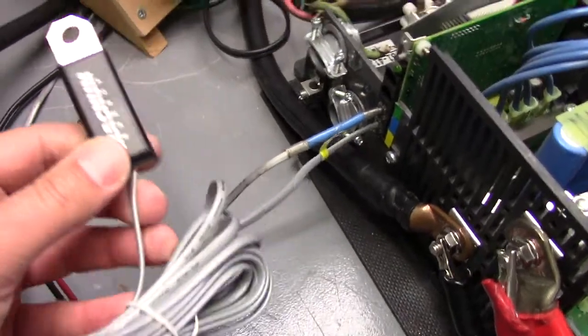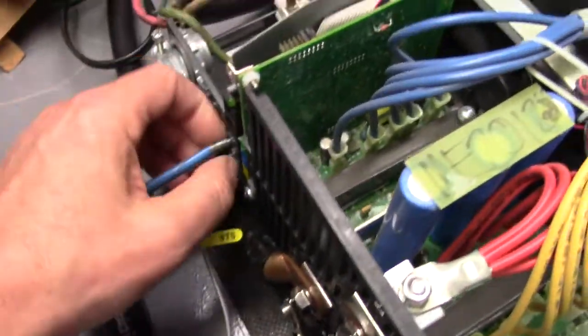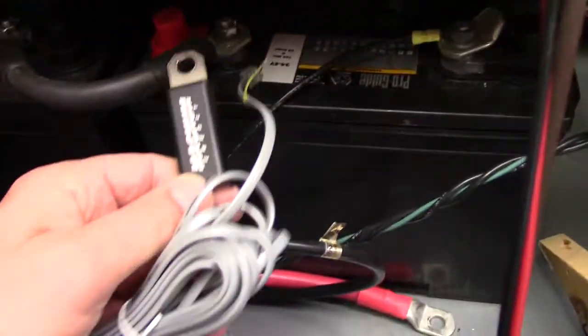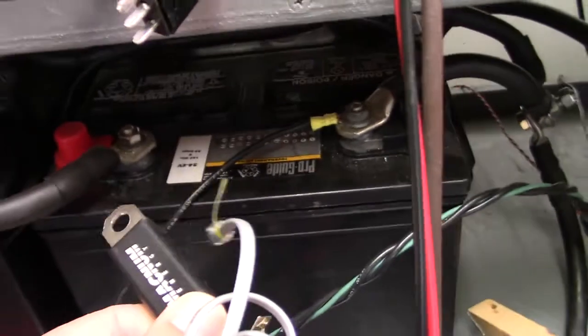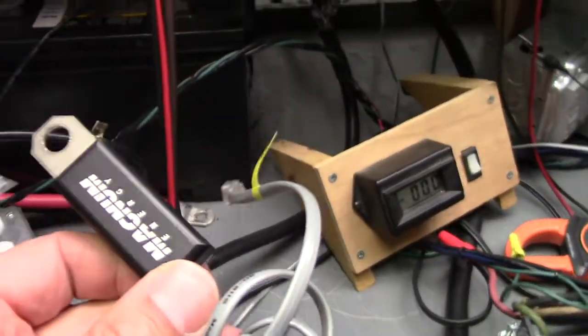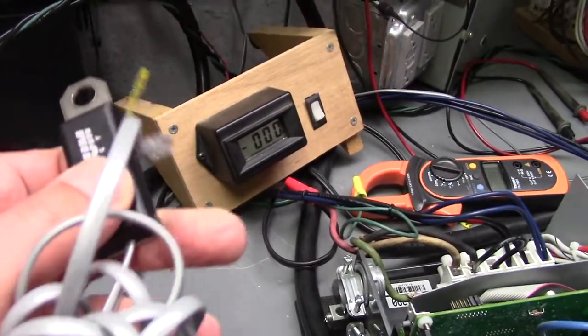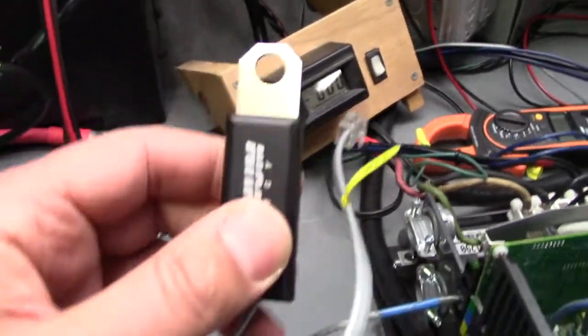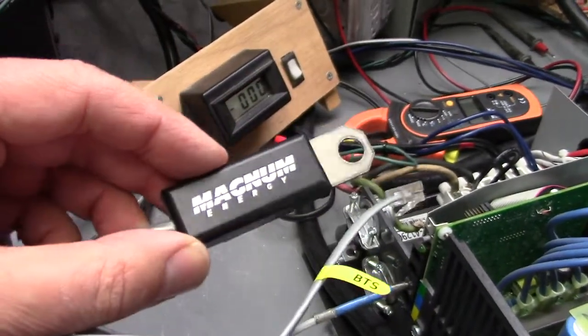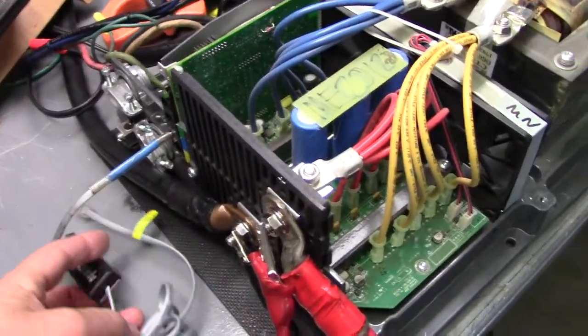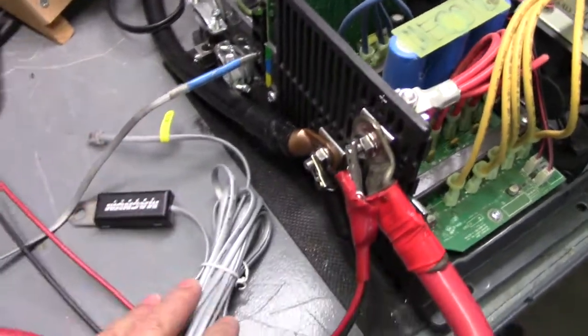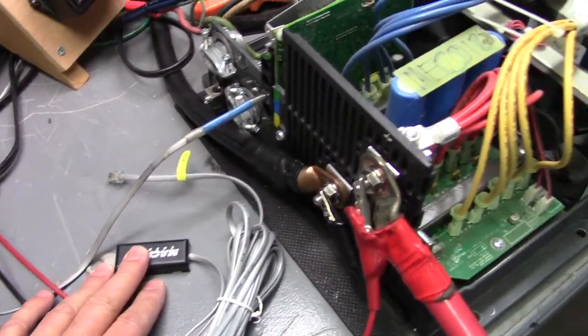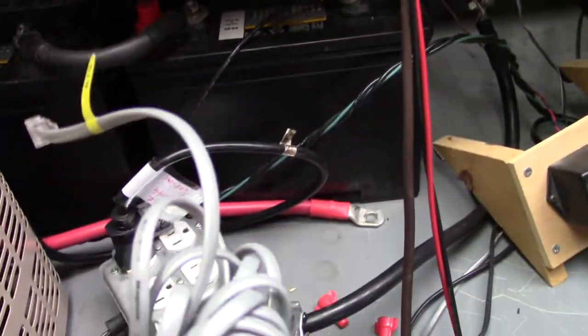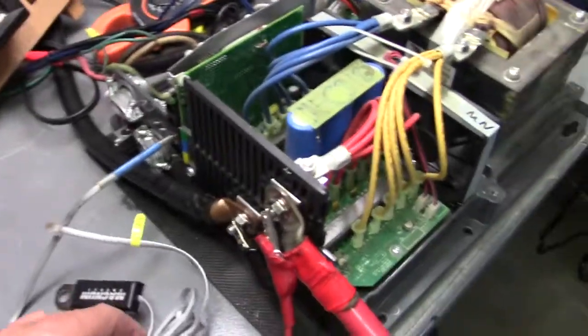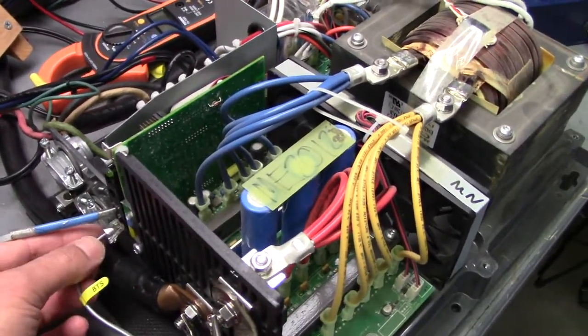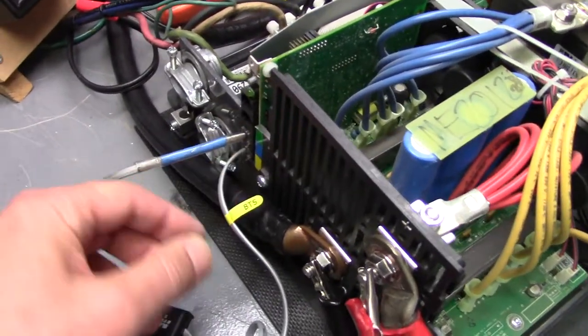And on these sensors, this normally gets bolted to a battery terminal. It's just for the purpose of picking up the temperature of that battery. This tab is not conductive to any of these wires. It should not be, or you're going to have a problem. It's simply to transfer the temperature to the sensor inside this case, and then the microprocessor in the inverter reads that temperature, and it will alter the charge cycle so that in the summertime you prevent overheating the batteries, and then in the wintertime it'll charge them a little harder to get them fully charged if they're cold. So the bottom one is the battery temperature sensor.